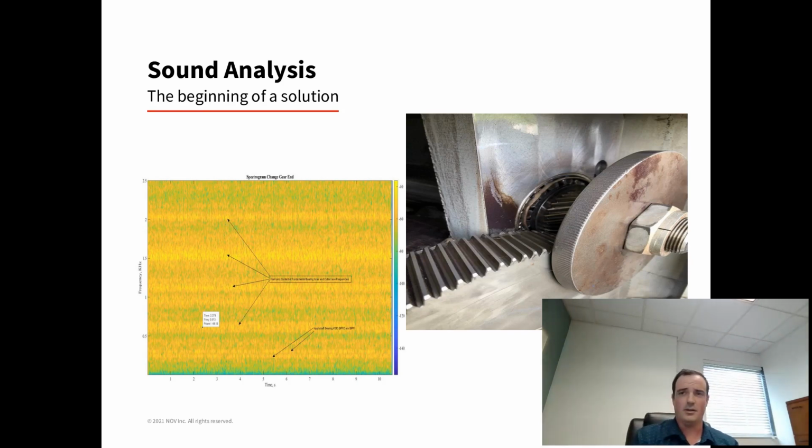Now, one thing you might be wondering, or you might be thinking about, is some of our equipment runs at really low speeds. We can also tell in the time domain, or in pulsing over time, if they have a failure at a really low speed. We found this to be really successful for telling a customer quickly what could be failing and helping them quickly get a solution. The goal here is when they see something that sounds bad, to tell them what they need to do and quickly get a plan of action going for them.